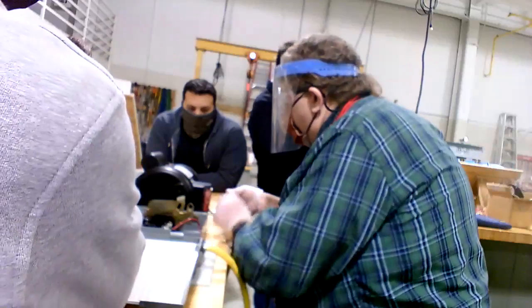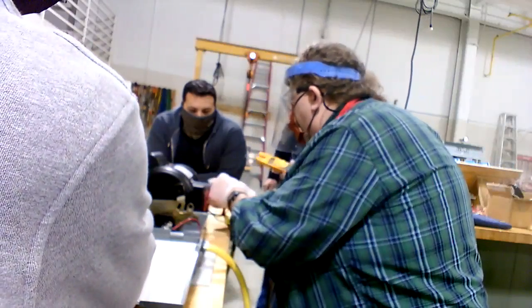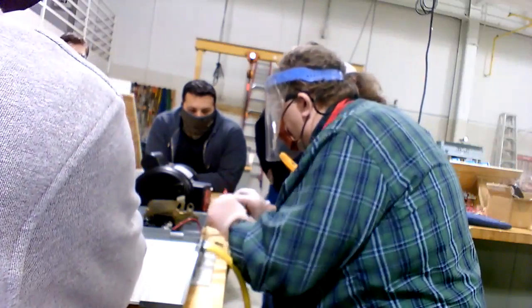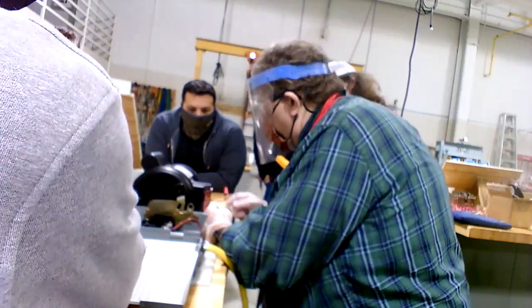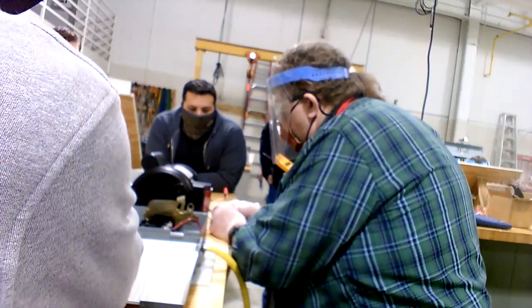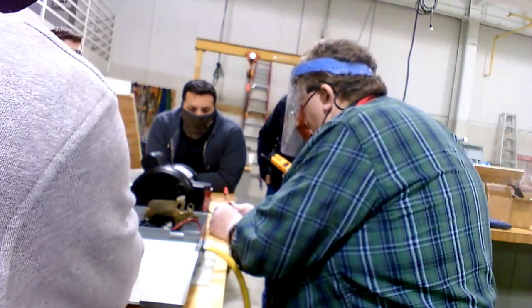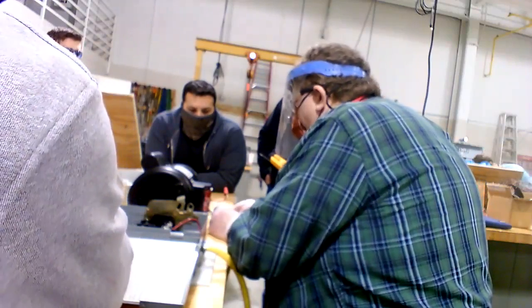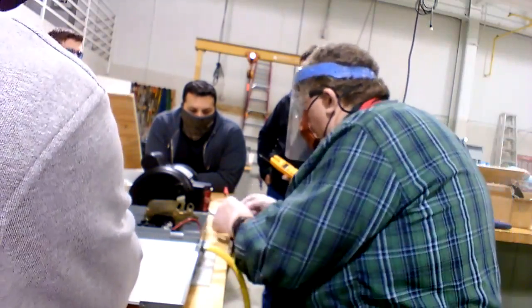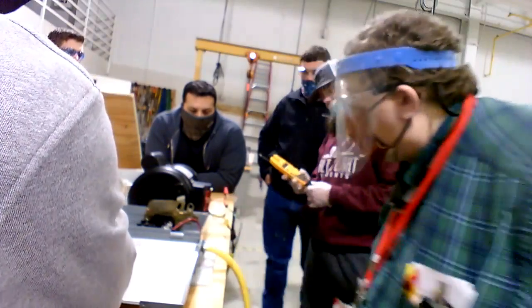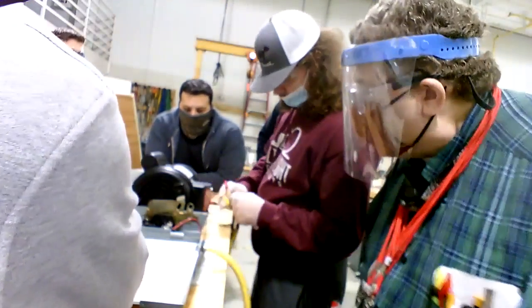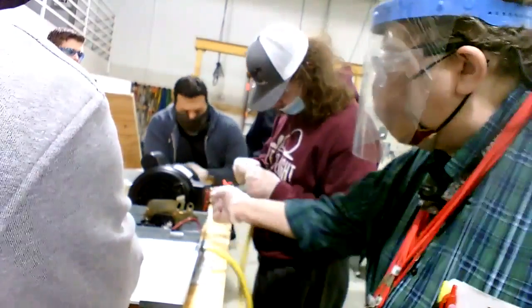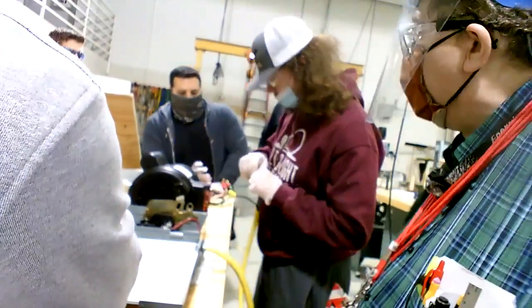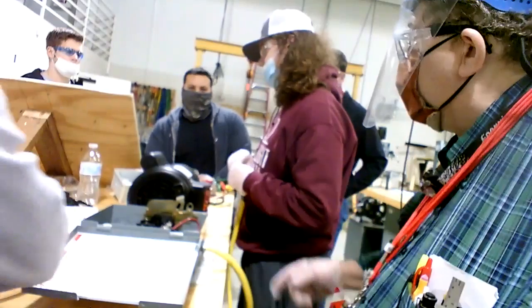Orange, red, white. Insulated, INS means insulated, it's just a wire nut, keeping them together, and yellow, black. You see how loose that is? You have to strip it a little bit longer, so it don't grab out again. We just take those apart. But you can't run it with a loose connection, that'll end up coming loose in the cab head, it'll arc and it'll short out. So.